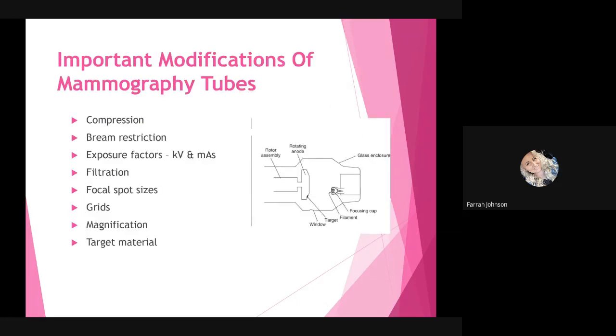So here are some important modifications of mammography tubes. Of course, what makes them different than, say, X-ray machines? Well, we have compression devices, beam restriction devices, and exposure factors such as kVp and mAs are going to be different. Filtration is slightly different. Focal spot sizes, grid use, magnification methods is another big one, and then also target material.